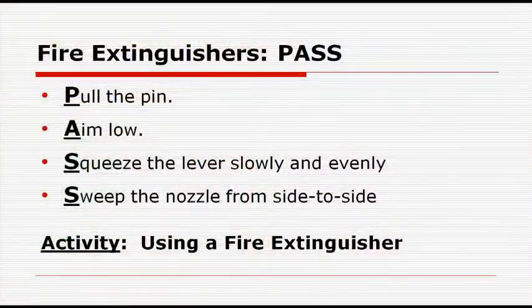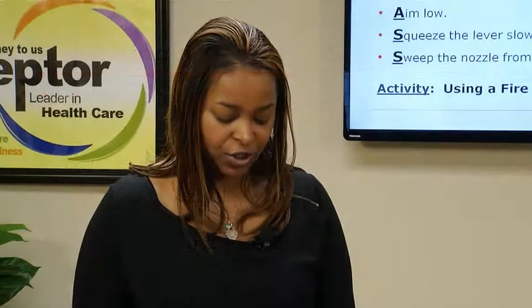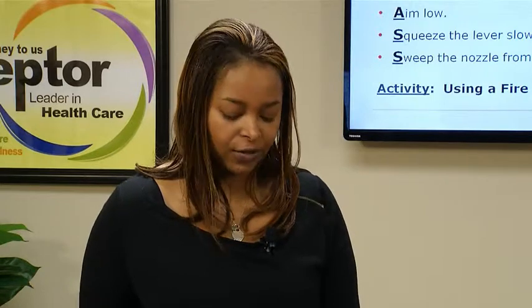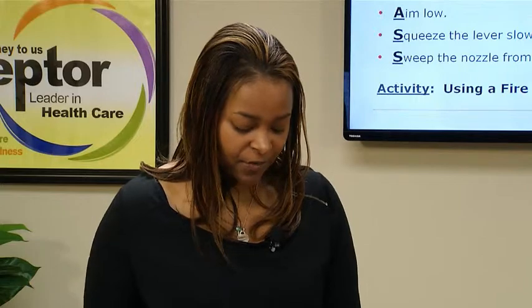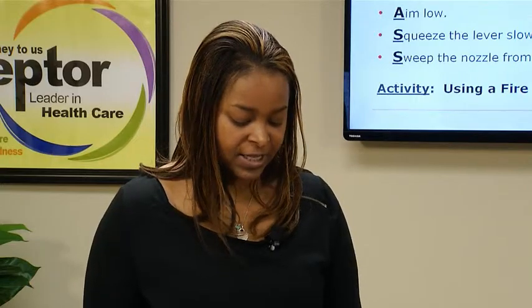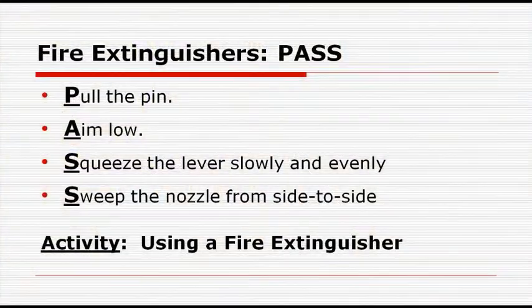Okay? So, some other things about fire extinguishers. If you can answer yes to all of the following questions, then you can use a fire extinguisher. What type of fire extinguisher is needed, and is it available? Can the fire be controlled? Have other staff, residents, and the fire department been notified? Have all residents been removed from the immediate area? Are you safe from any toxic smoke produced by the fire? Do you have a means of escape? And are you capable of lifting and using the fire extinguisher?